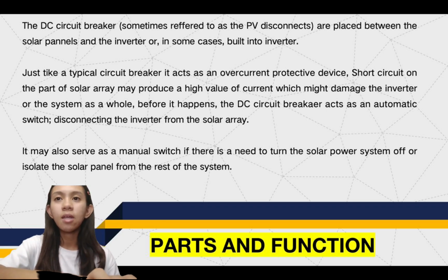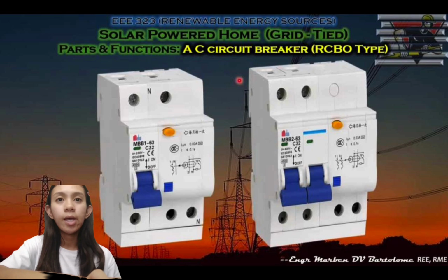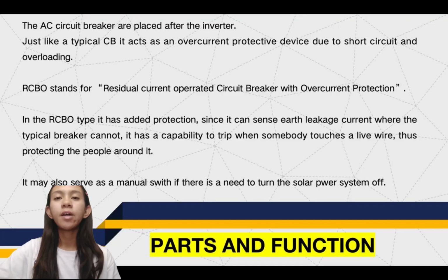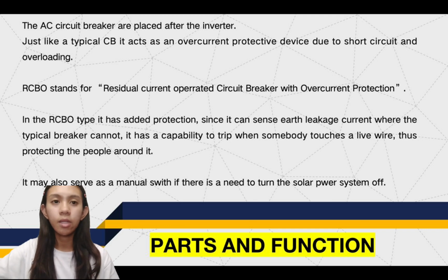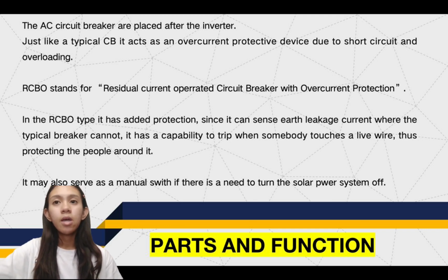So, next natin is AC circuit breaker. AC circuit breaker are placed naman siya after the inverter. So, kanina yung DC circuit breaker between solar panel and inverter. Just like a typical CB, it acts as an overcurrent protective device due to short circuit and overloading.